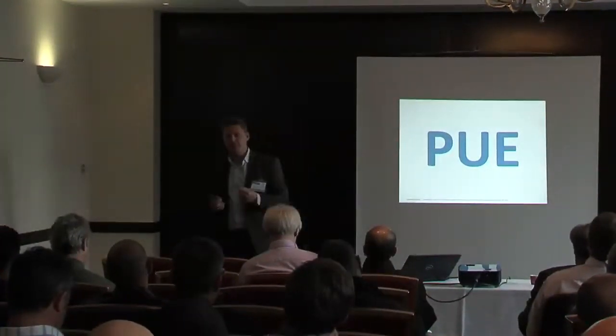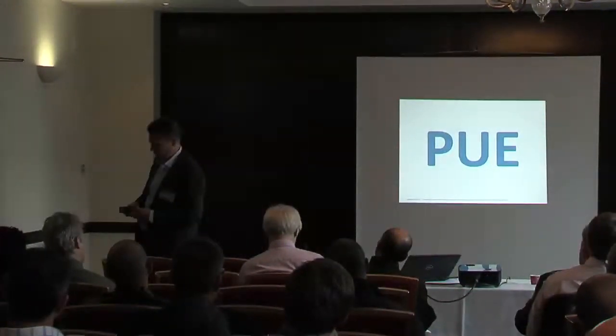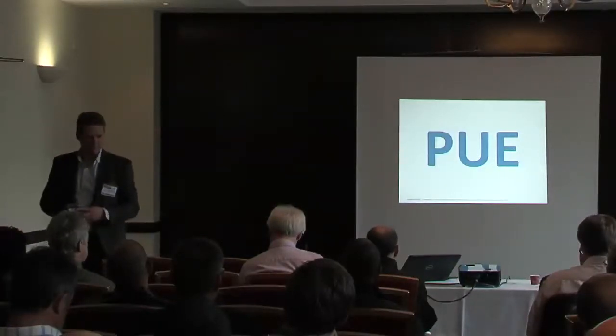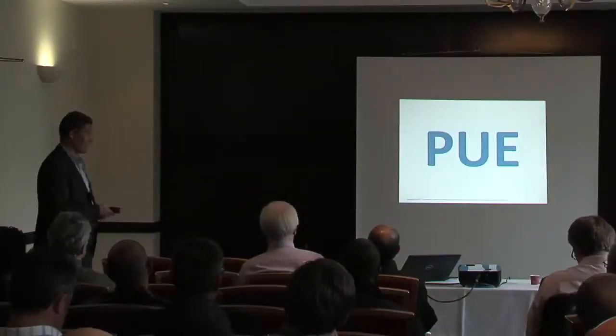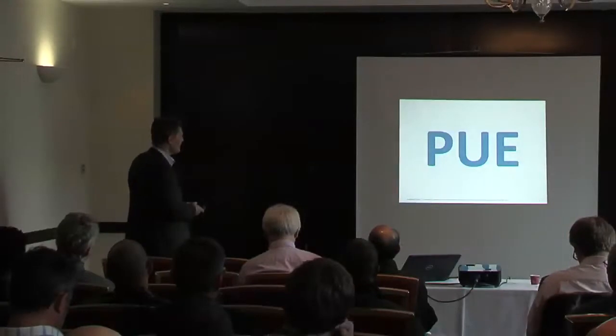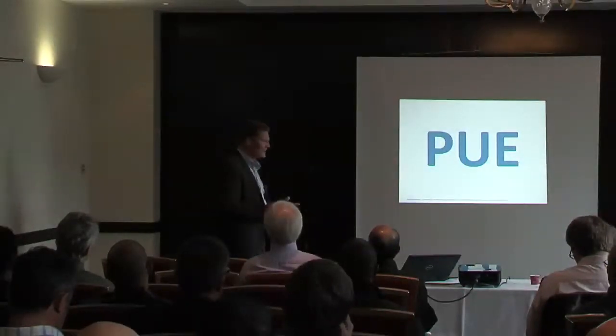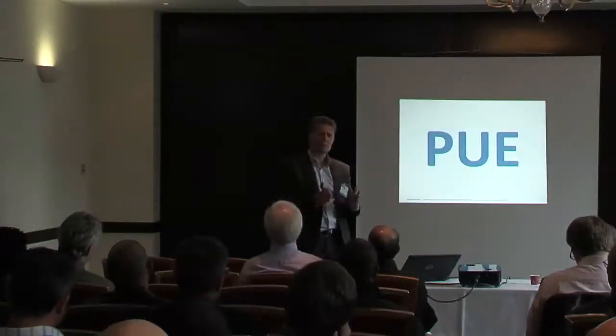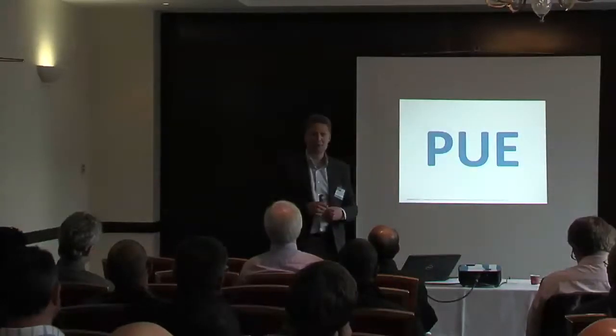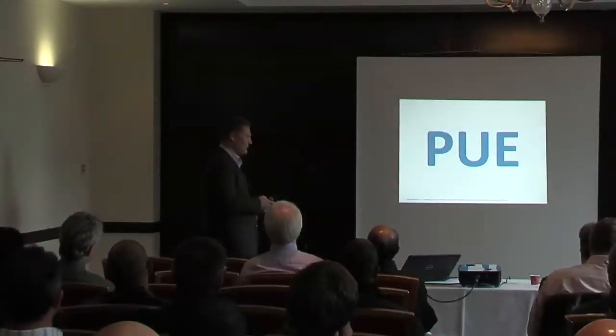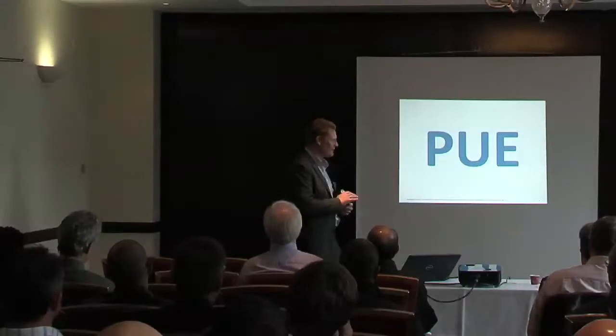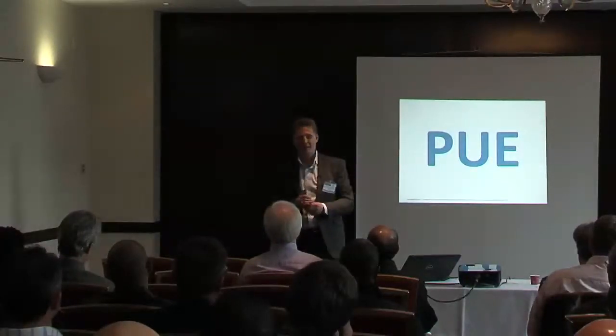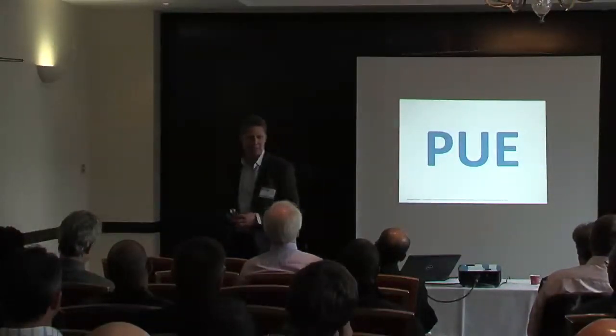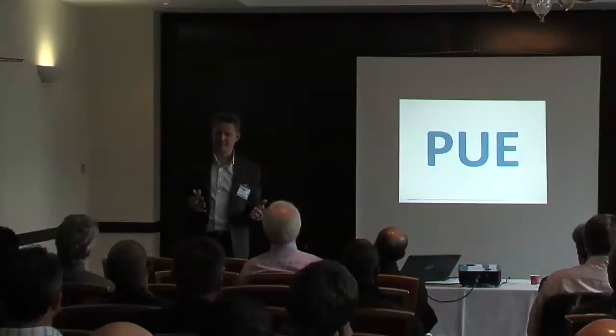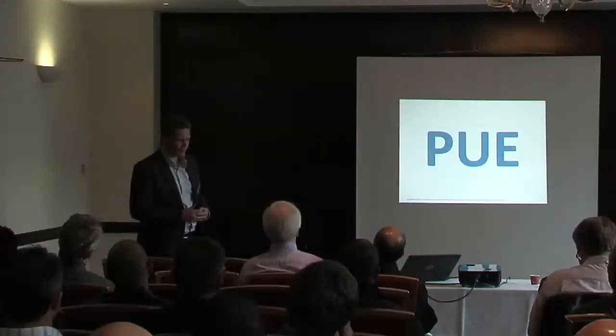PUE is one of those very misunderstood figures, if you ask me. I saw some claims last week from the US claiming a PUE of 1.012. Well, good for you, how did you measure that? It was a point-in-time measure under ideal conditions, and by the way, they left out half of the things we normally put in the equation. Well, fantastic, then everybody can get a good PUE.